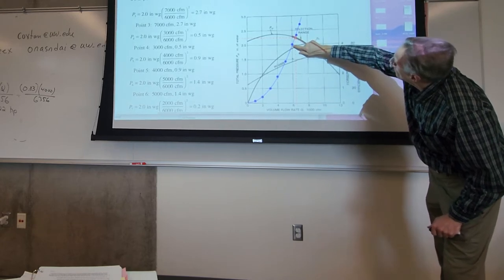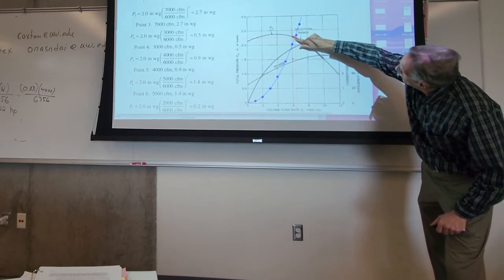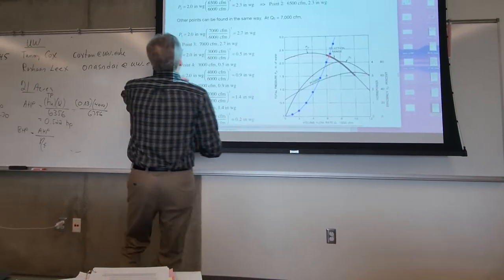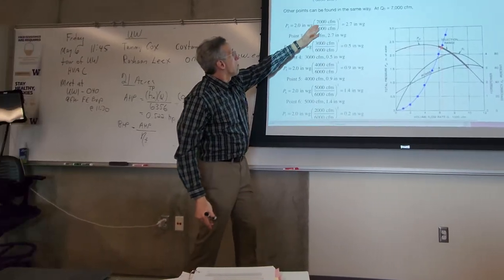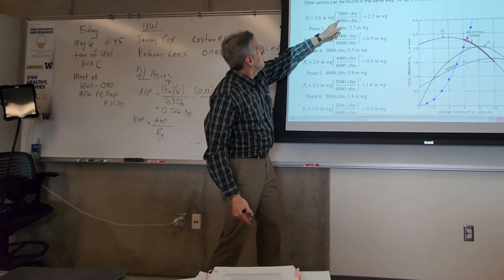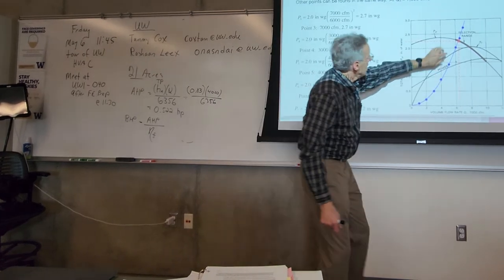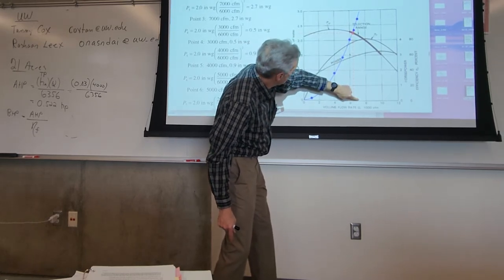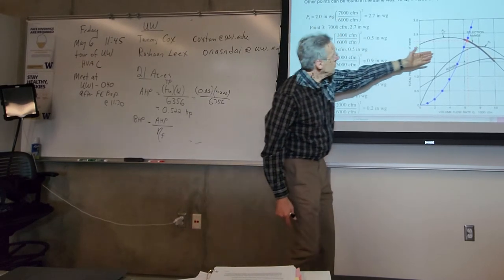6,500, and here, this point here. So it's a little bit above my design point, but now I have a second point. And then I can do a third. How about if we go to 7,000 CFM? What if I need 7,000 CFM? Originally 6,000 at 2 inches of water. What's my new pressure going to be? Well, 2.7 inches. So we've got 2.7 inches over here, and 7,000 CFM.